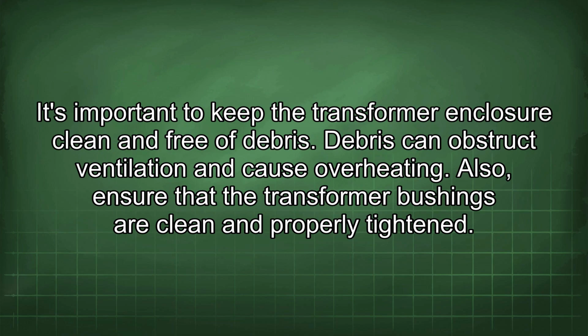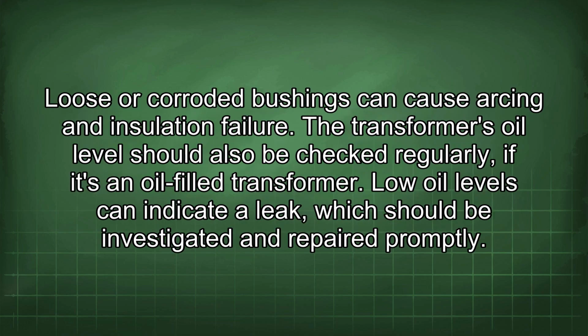It's important to keep the transformer enclosure clean and free of debris. Debris can obstruct ventilation and cause overheating. Also, ensure that the transformer bushings are clean and properly tightened. Loose or corroded bushings can cause arcing and insulation failure.